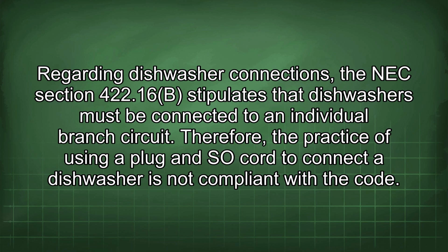Regarding dishwasher connections, the NEC section 422.16b stipulates that dishwashers must be connected to an individual branch circuit. Therefore, the practice of using a plug and SO cord to connect a dishwasher is not compliant with the code.